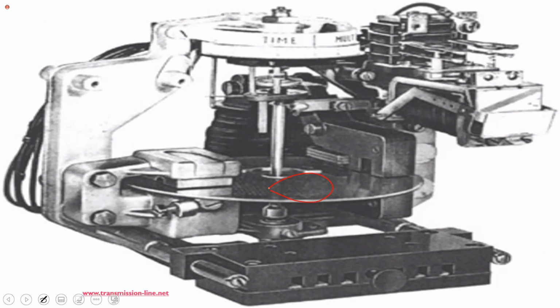The greater that flux, the faster the disc will turn. So in other words, if you have more current, because the voltage will be fixed, as the current increases, that flux will increase. And so the torque on the disc will increase. All right.